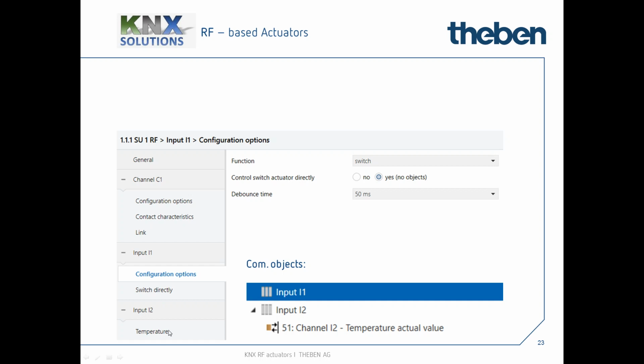That means here I can link a temperature probe to this communication object, and convert the temperature sent from the binary input and send it to the KNX bus system, the KNX structure, to give it to a heating actuator - or if you take a heating actuator flush mounted on its own, you have one of the smallest heating actuators in the market. But this you will see later on in a specific slide.